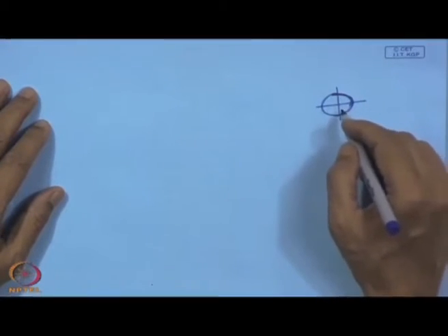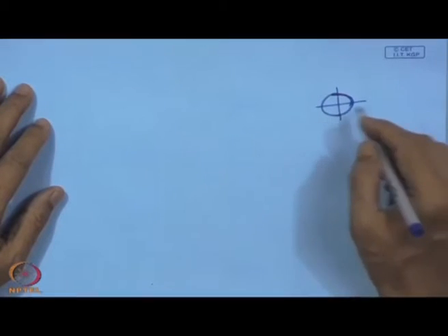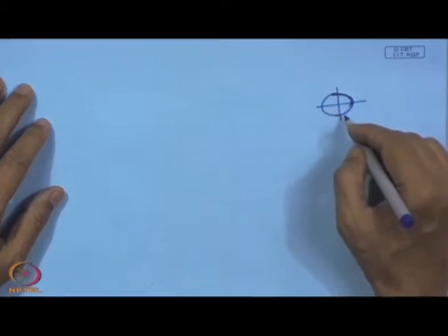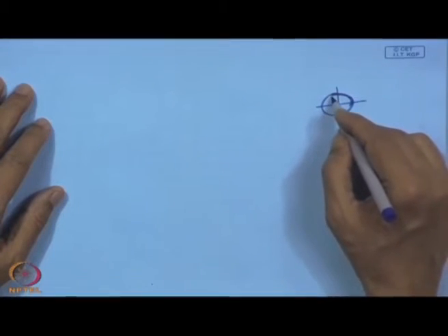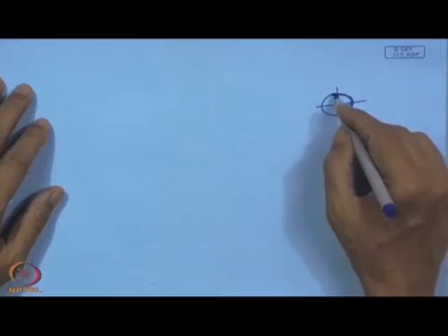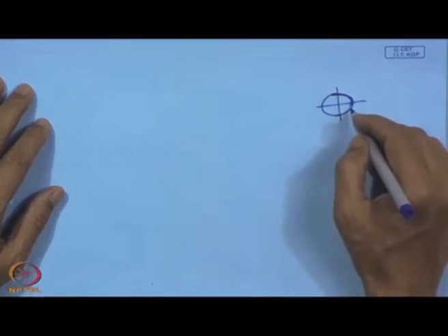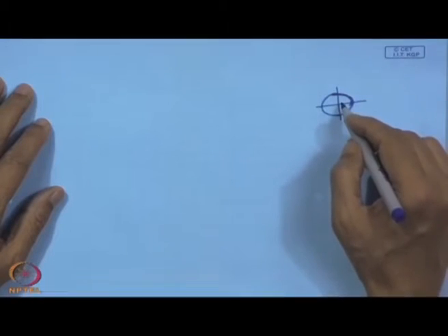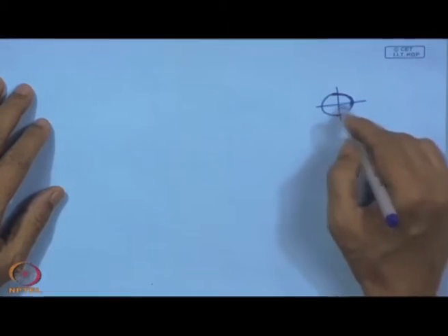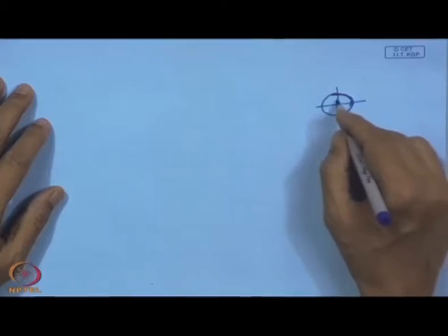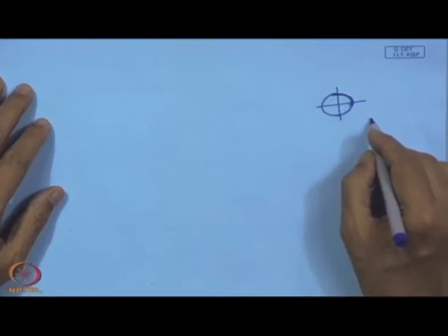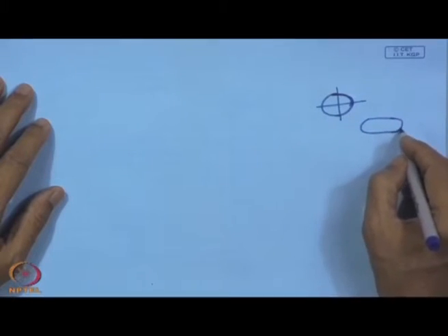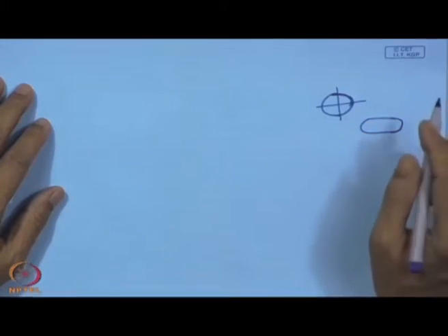When this elliptical tube is subjected to high pressure, its dimension changes and it becomes more circular in nature. That means the difference between the major axis and minor axis will be further narrowed. However, when it is subjected to high vacuum, it will be flattened and this elliptical shape will change, and again there is some change in the dimension.